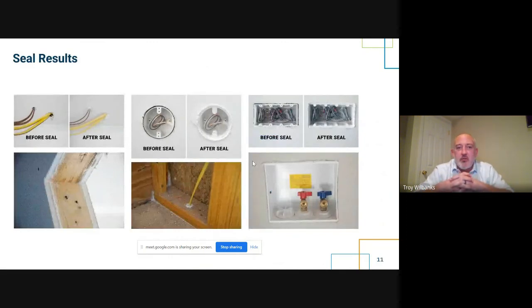Here are some really good pictures of what a seal looks like. But it does bring up some questions: before and after the seal, what happens when they move the wires around? You can see in the middle picture there's a little build up. What are the rest of the trades going to do when they come in? So really, our sealant has a plus or minus 20% flex rating. So the electrician could come in and move those wires around, and it's not going to degrade the integrity of the seal. And it's 100% sandable and paintable, so the drywall crew and paint crew can come back and do everything just like they normally would.